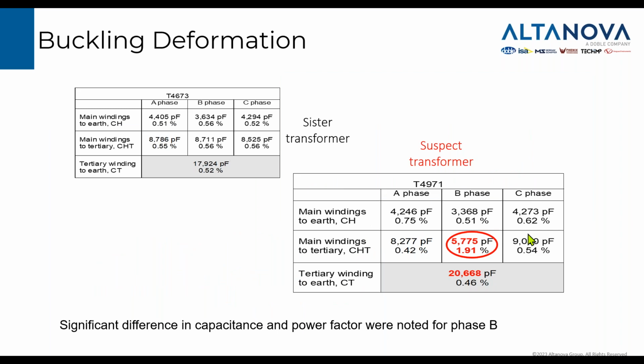So the transformer was subject to testing. Power factor tests show that B phase, measured between main windings and tertiary, showed much lower capacitance than that of the sister transformer, and much higher power factor than that of the sister transformer. At the same time, tertiary winding capacitance to ground was higher than that of the sister transformer. So we had quite a strong indication that something is wrong here.